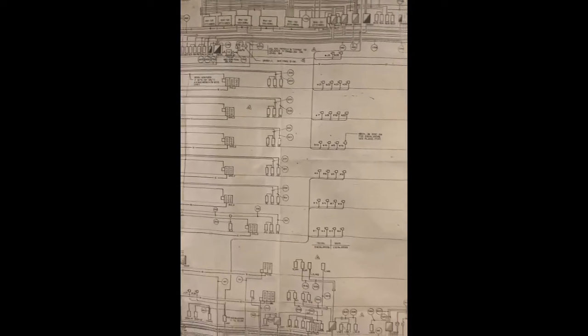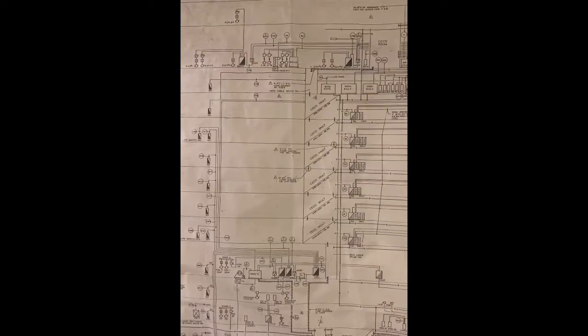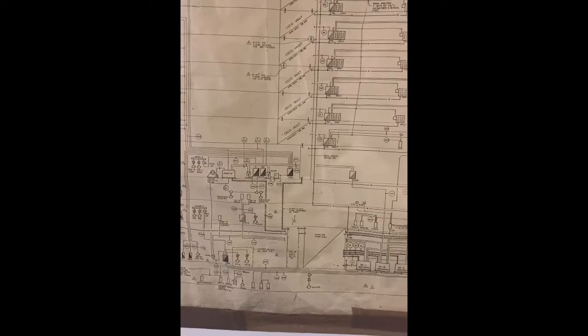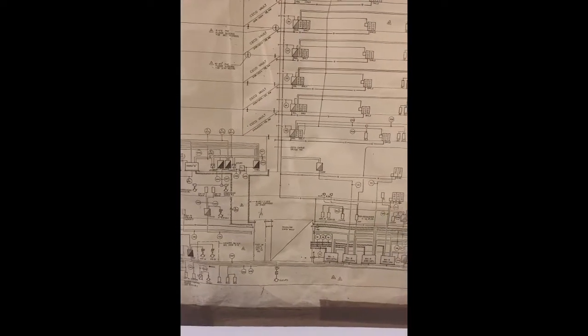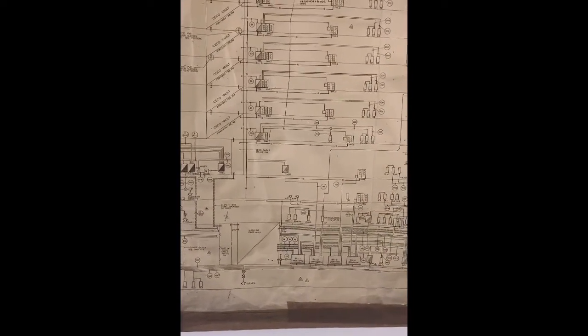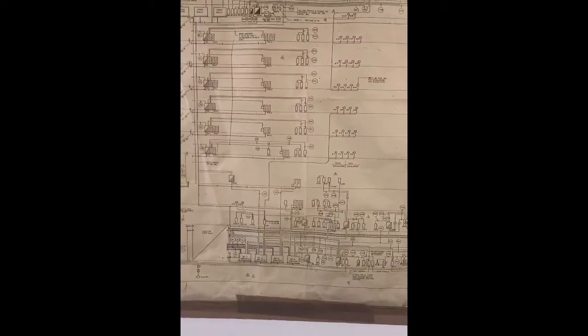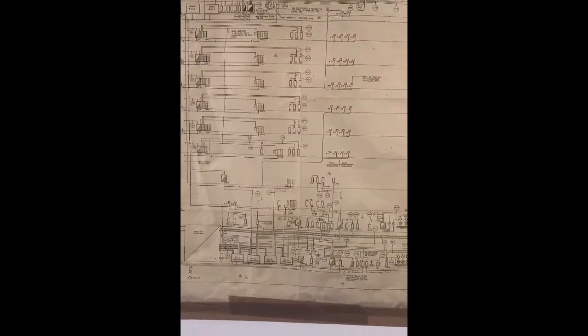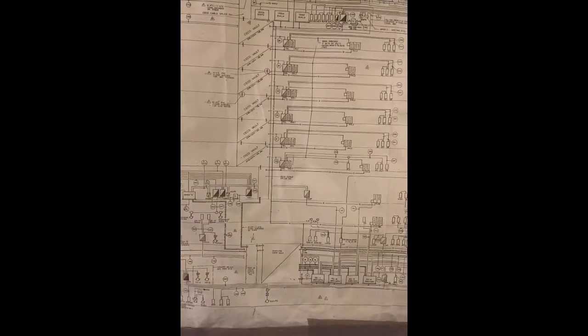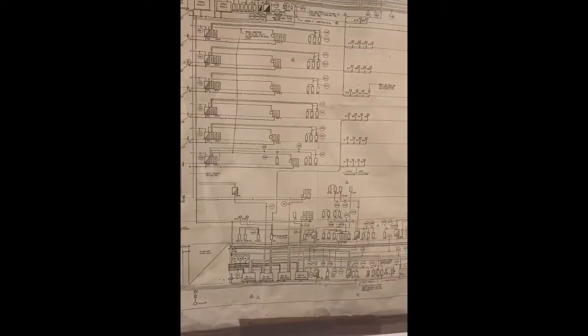But this is basically my entire building's electrical distribution on one sheet of paper, allowing me to easily trace back and find where different loads are being powered, simply because there's multiple layers of protection. We're always most familiar with the closest local disconnect for a piece of equipment, but because of the multiple layers of protection, if something were to fail in between, you would definitely want to know where the hell to go in order to remedy that situation.